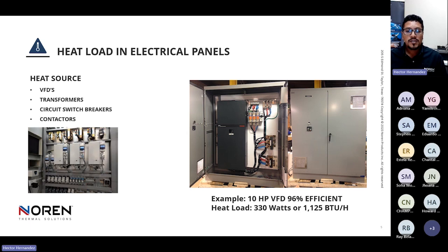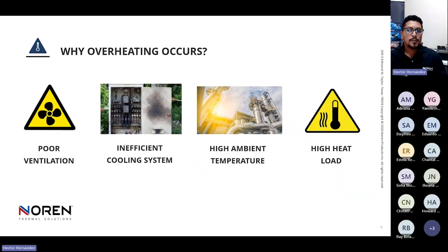As you can see in the picture, it's not just the VFD. There are other devices connected to it that are adding heat into the electrical panel. The reason we enclose them in an electrical panel is because these devices are really sensitive to external contaminants like dust, moisture, and corrosive chemicals. This is why we have heat inside electrical panels.